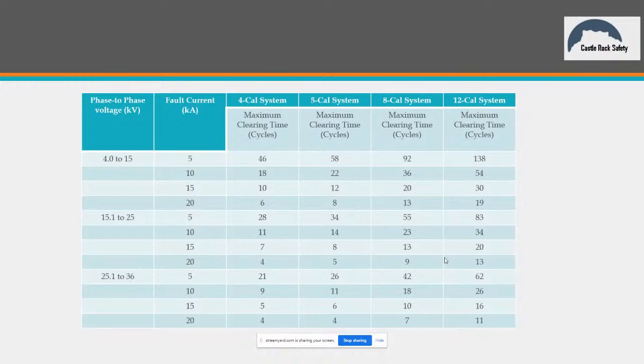So let's say that someone is working on an overhead line. We've got 12,470 volts, and let's say that our fault current on that line is 10 kA, 10,000 amps, and I've got a maximum clearing time of 9 cycles. Okay, so if I've got 10,000 amps of fault current and 9 cycles of clearing time, where do I fall? That tells me that I'm in a 4 calorie category. The maximum exposure I'm going to have is 4 calories.